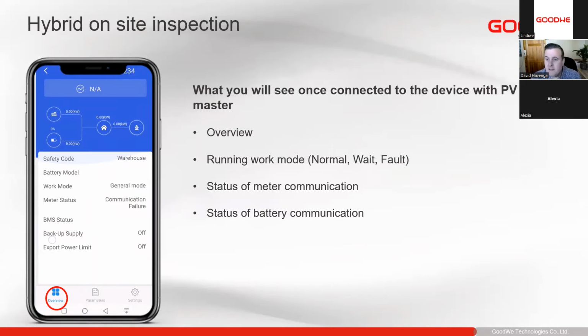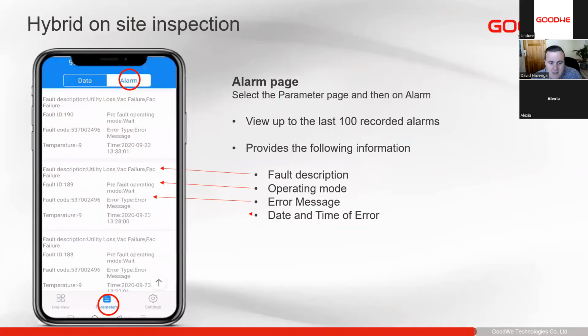Next, on site. So if you have gone on site to help the customer see what's wrong, we can connect to PV Master on the device. So if there have been any alarms or anything like that, let's see. When you open PV Master, we're in the overview. Here we can see the general running status, the work mode, and the status of the BMS, the smart meter, and all of that. Next, you go to parameters. Parameters at the bottom will start in the data tab. You then go to alarms. So you go to parameters and then alarms.